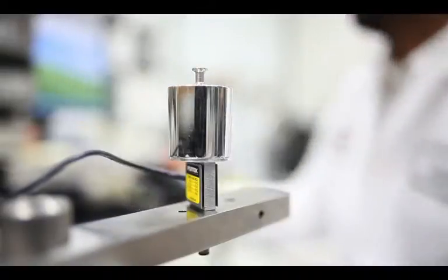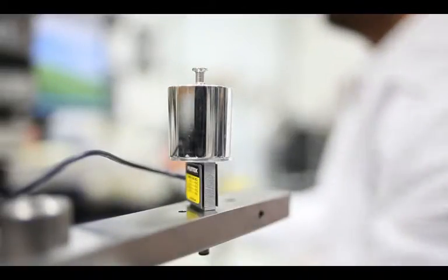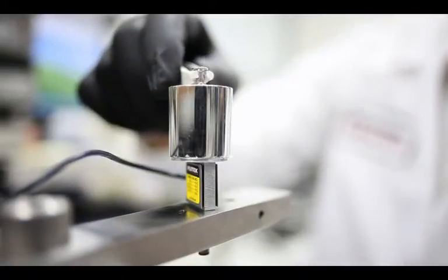The second advantage is the overload stop capability. Normal sensors have 150% of safe overload; this has 1,000% of safe overload in both tension and compression. The advantage is that if a technician accidentally overloads it during installation, they won't damage the product. We've actually tested this—we took a 100 gram sensor, loaded 50 pounds on it in tension and compression, and it didn't even change the specifications or the sensitivity factor.